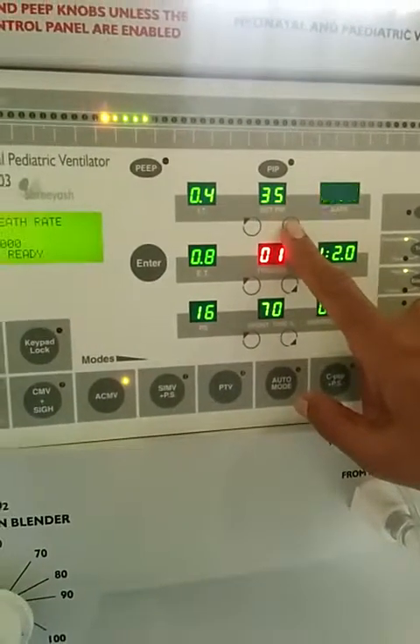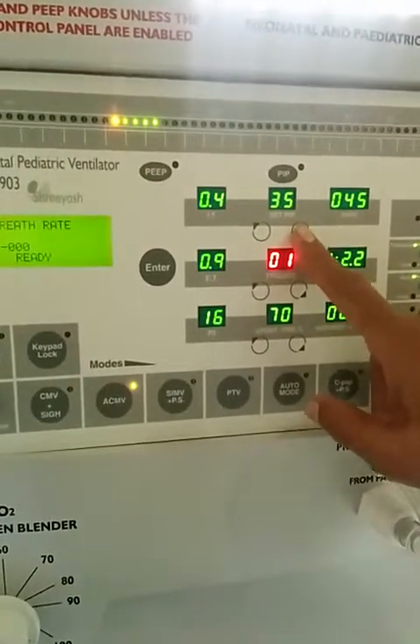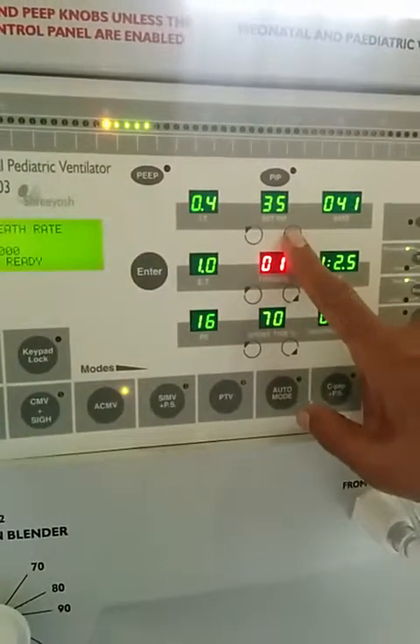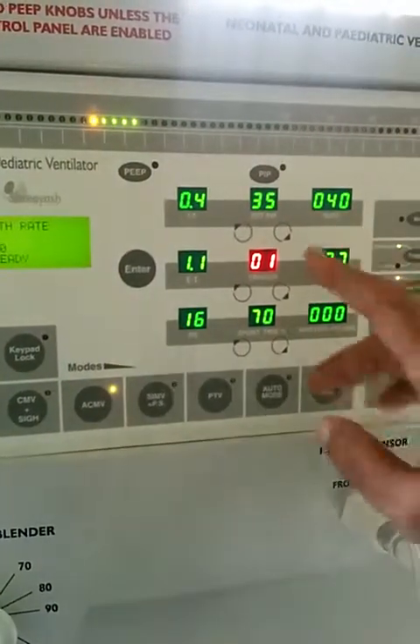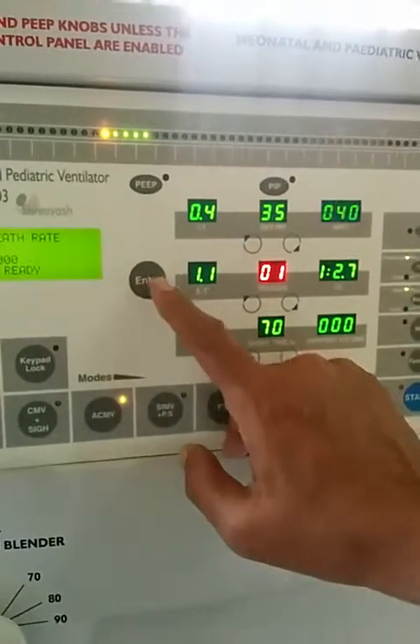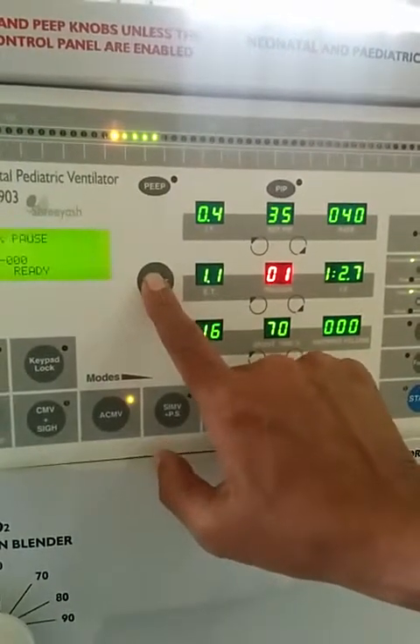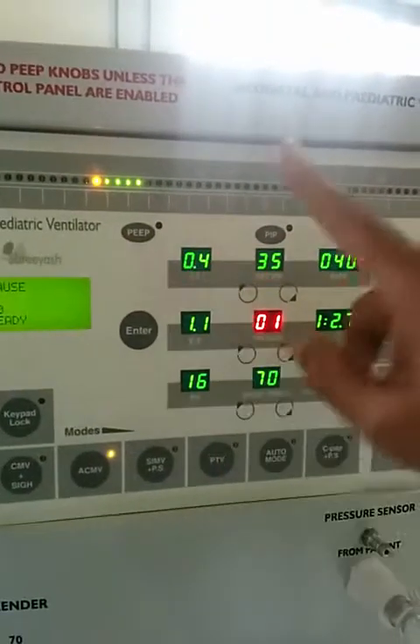So this can be set from 4 breaths per minute to 120 breaths per minute. As I said, we are setting a parameter for a newborn baby, so I'll set the breath rate of 40 breaths per minute. Once I set it, I need to acknowledge it by pressing the enter key. So I press it again. Now it is set. So you have set the inspiration time, you have set the breath rate.